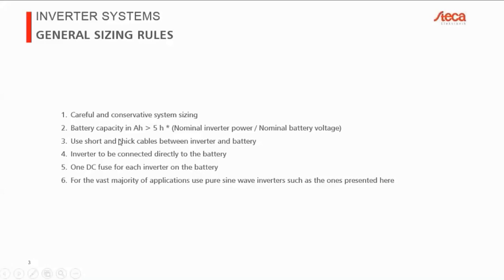So our recommendation is to calculate your battery capacity in amp hours. You take 5 hours times the nominal inverter power. So if you have a 1 kilowatt inverter, then you take 1,000 watts. You divide that by your nominal battery voltage. So this is 12, 24, or 48 volts. And then you get your minimum battery capacity in amp hours. So your battery should have this capacity or larger at the voltage you've chosen.